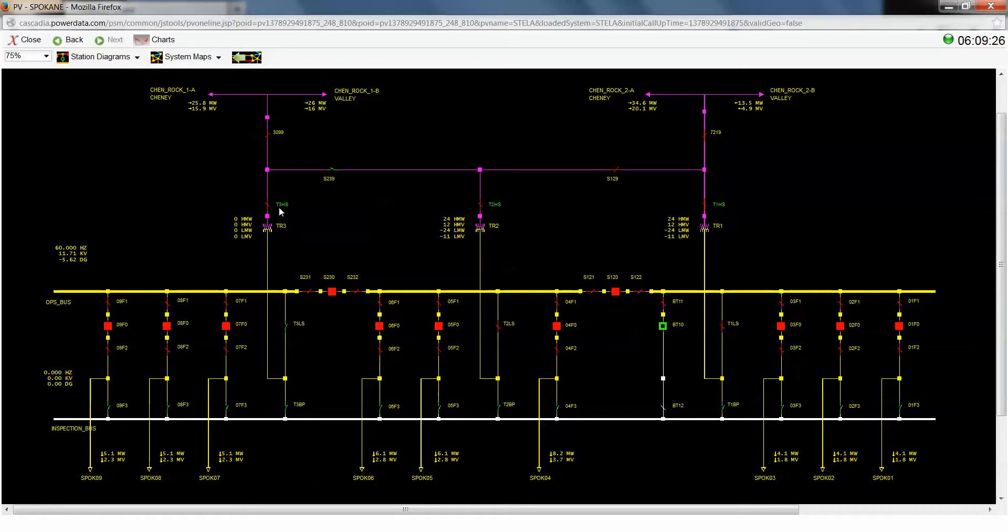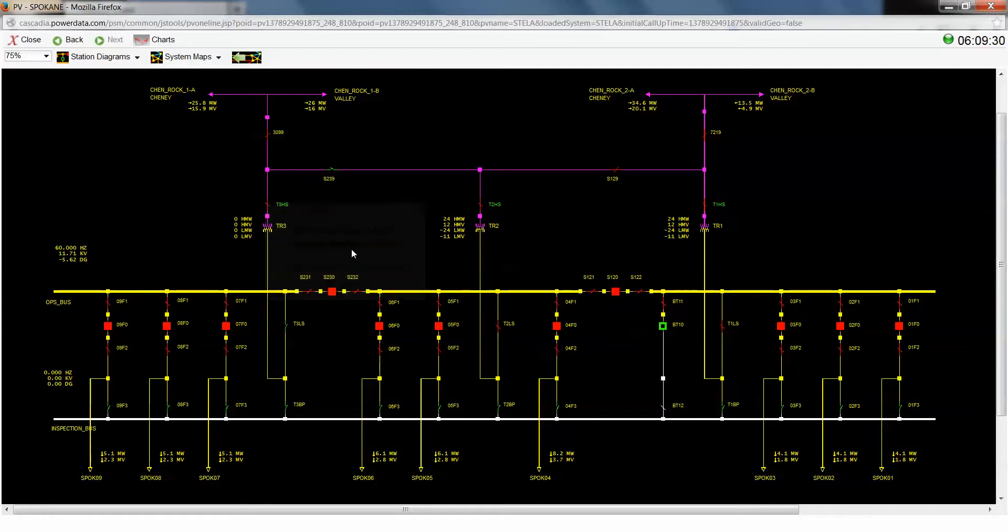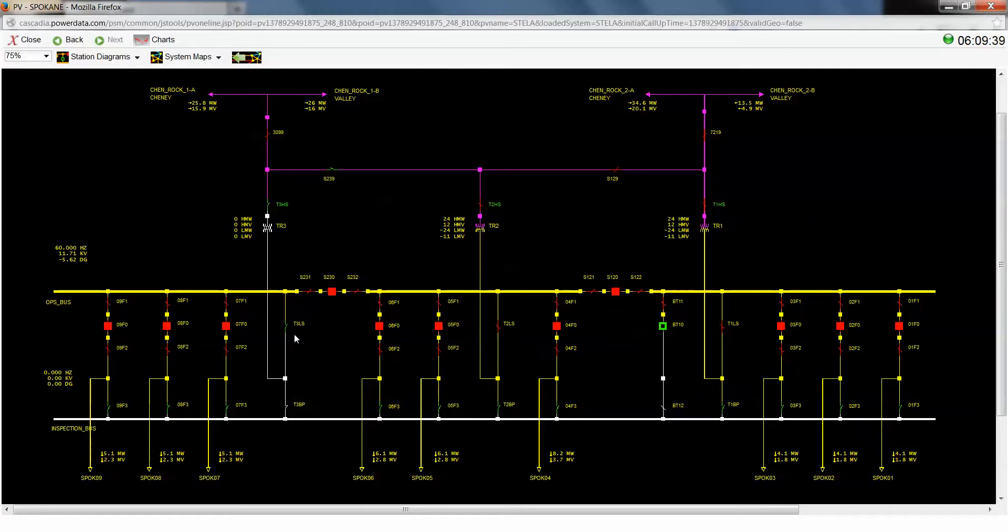So the very last thing we're going to do is we're going to open our high side switch for our transformer three. And you can see now that this transformer has turned white, the associated bus work has turned white, and all three of our switches are open.